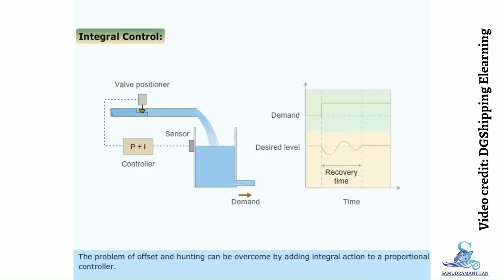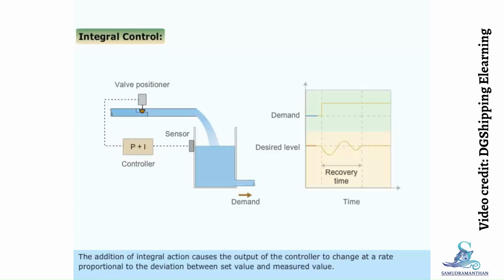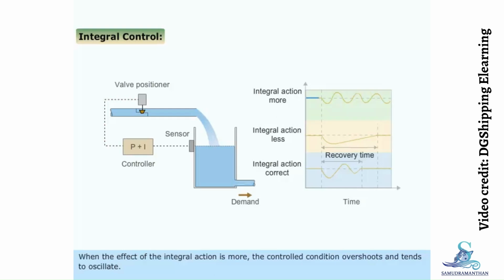The problem of offset and hunting can be overcome by adding integral action to a proportional controller. The addition of integral action causes the output of the controller to change at a rate proportional to the deviation between set value and measured value. When the effect of the integral action is more, the controlled condition overshoots and tends to oscillate. When the effect of the integral action is less, it takes a longer time to achieve the controlled condition. Correct application of integral action will have a slight overshoot, but the controlled condition is achieved quickly.